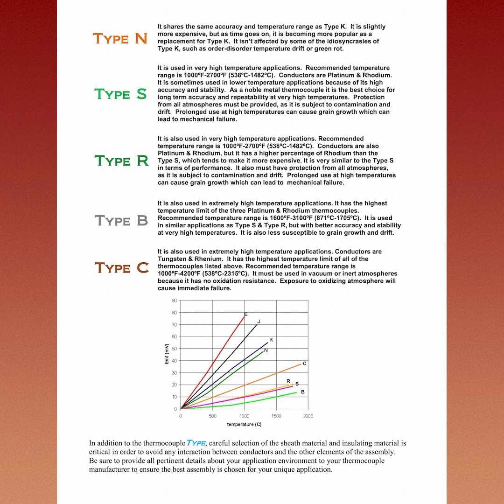Type B is also used in extremely high temperature applications. It has the highest temperature limit of the three platinum and rhodium thermocouples. Recommended temperature range is 1600 to 3100 degrees F or 871 to 1705 degrees C. It is used in similar applications as Type S and Type R, but with better accuracy and stability at very high temperatures. It is also less susceptible to grain growth and drift.